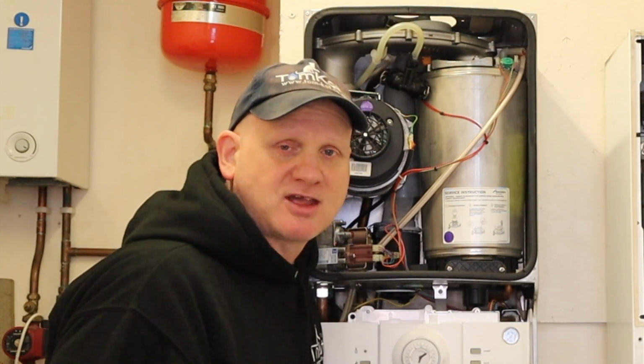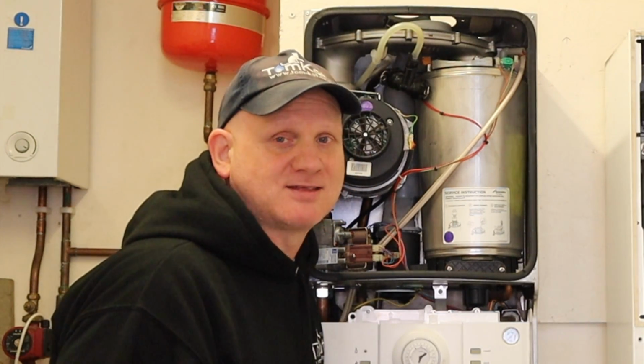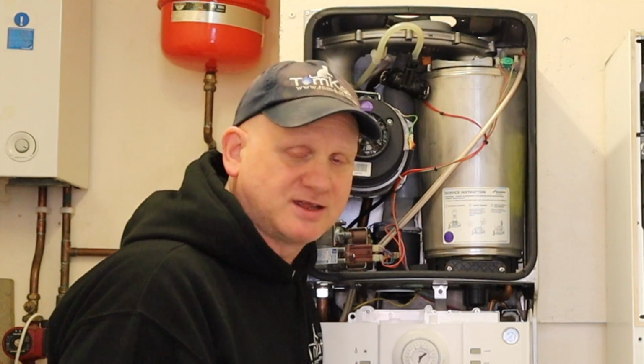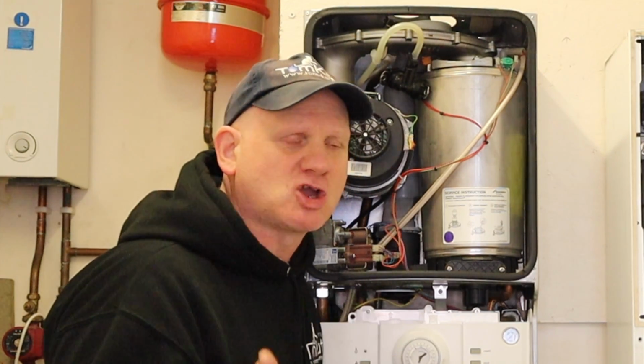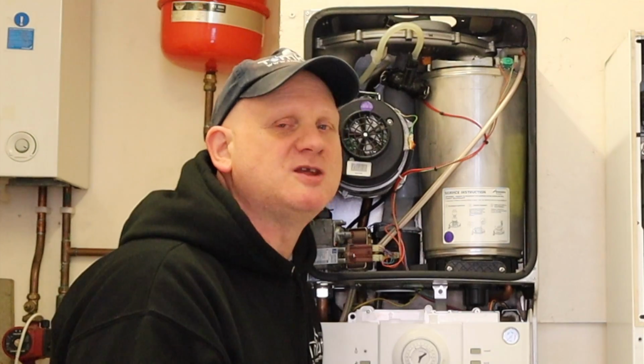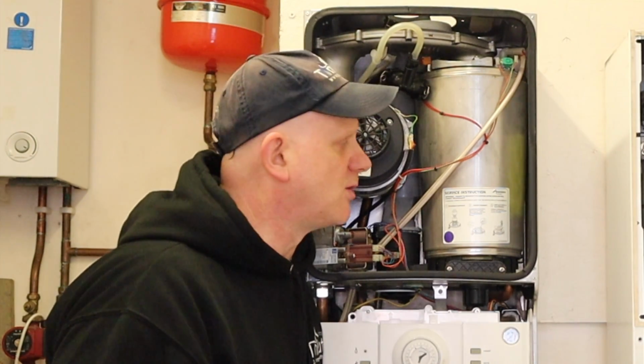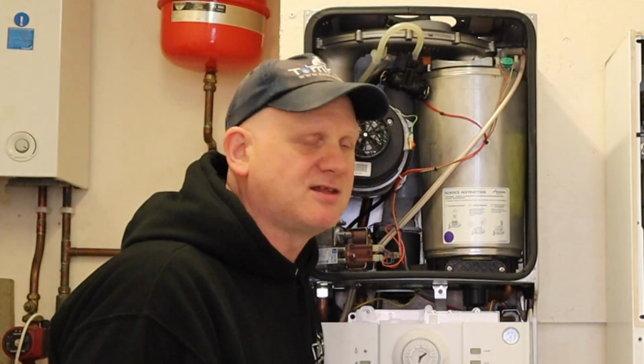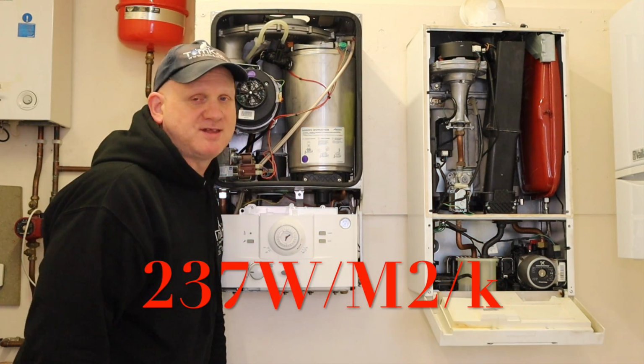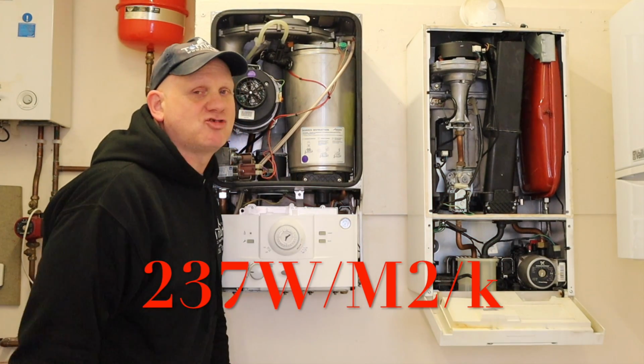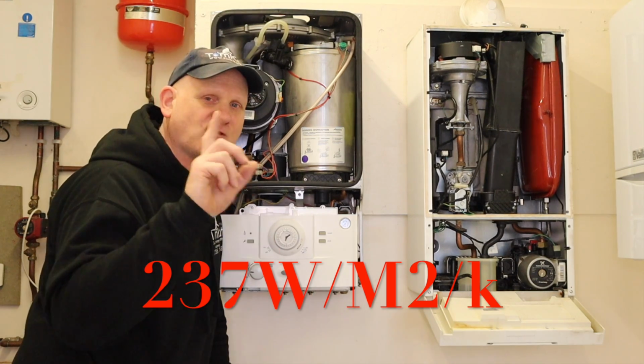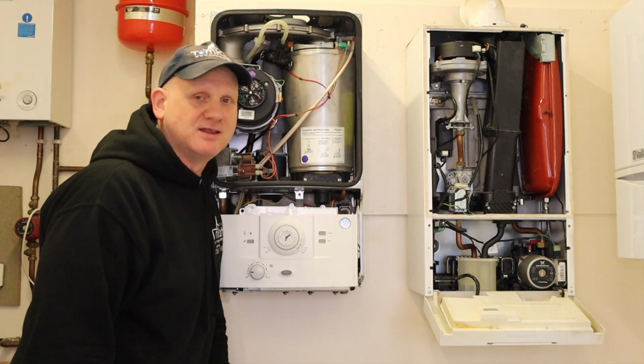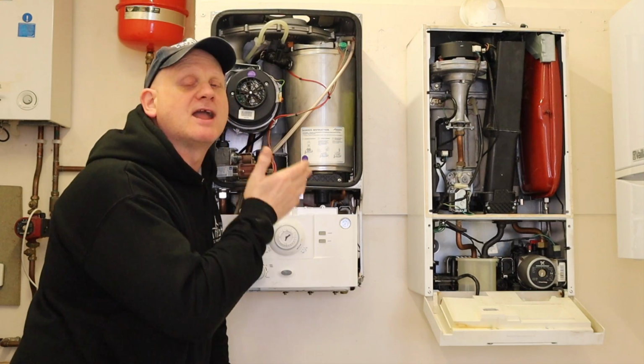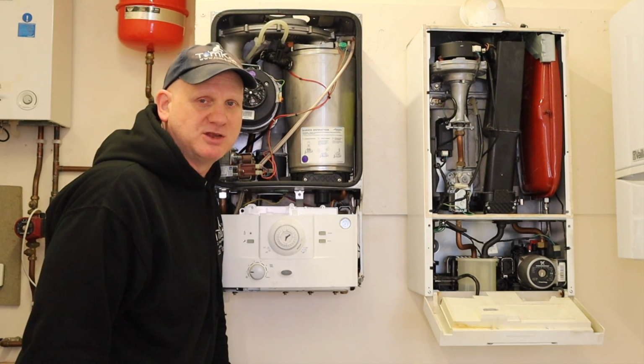Now these aluminium heat exchangers are very, very light compared to cast iron and stainless steel heat exchangers. So that's why they are commonly used. They also can be cheaper, not all the time, but they can be cheaper than stainless steel. So again, that's why a lot of manufacturers use them. But the main reason for manufacturers using them is their thermal conductivity. And it is said an aluminium heat exchanger's thermal conductivity is 4.5 times better than a stainless steel one. So that's why a lot of the major manufacturers use aluminium.